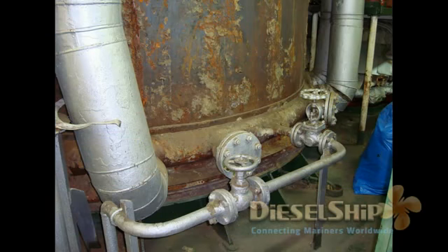So here are some pictures of boilers which I worked on. The boiler shown over here is completely ripped off. We were doing some retubing work with some Greek fitters, so this picture was taken at that time. Let me explain some components which are visible in this picture. This is the water ring, and these are the downcomers. These come from the steam and water drum, and the downcomer brings the cold water to this water ring. From the water ring you have tubes inside the boiler which generate steam and put it back to the steam drum. And what you see over here is the hand hole, and after emptying the boiler you can open this and clear the sludge out.